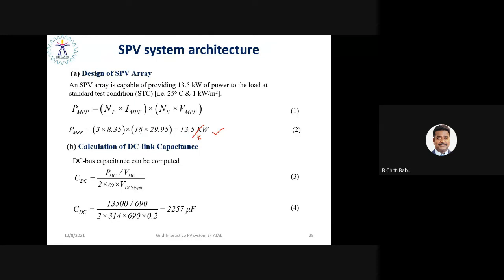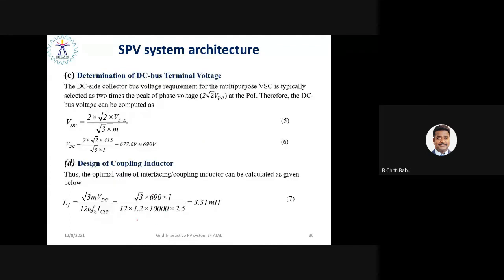And the DC link capacitance would be 2257 microfarad in order to have a DC link voltage of 690 volts, assuming the DC ripple would be 20% of the actual DC link voltage. The DC is about 690 volts, with a line to line voltage of 415 and assuming the modulation index is about 1. The coupling inductor should be 3.31 millihenry in order to reduce the current ripple on the inverter output current, with the current ripple about 20% and the switching frequency assumed to be 10 kilohertz.